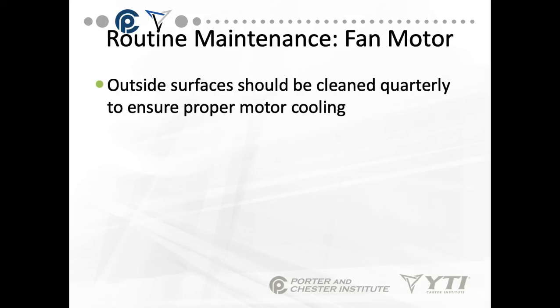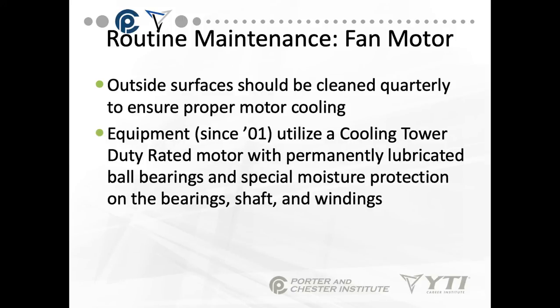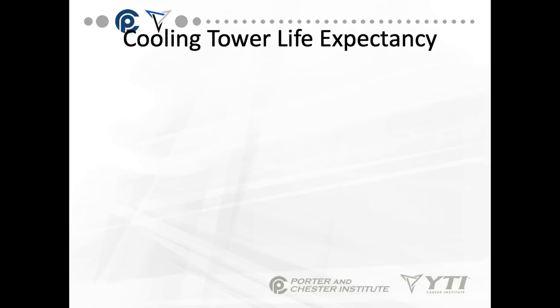Okay, outside surfaces of the motor should be cleaned to ensure proper motor cooling. Equipment since 2001 will use a cooling tower rated motor that has permanently lubricated ball bearings and special moisture protection on the shafts and windings. So if you have a cooling tower prior to 2001, you'll have to look and check out maintenance.